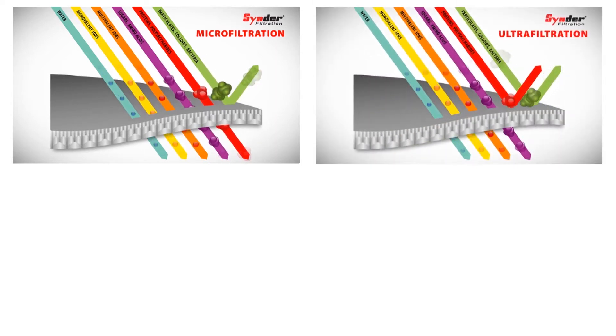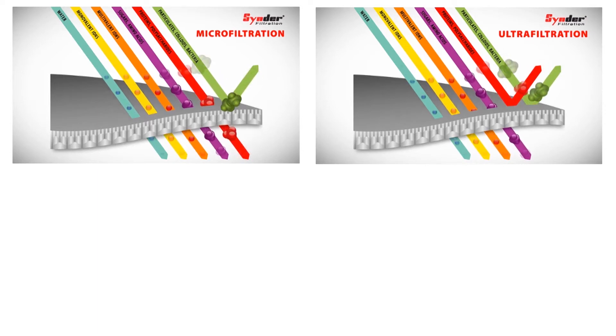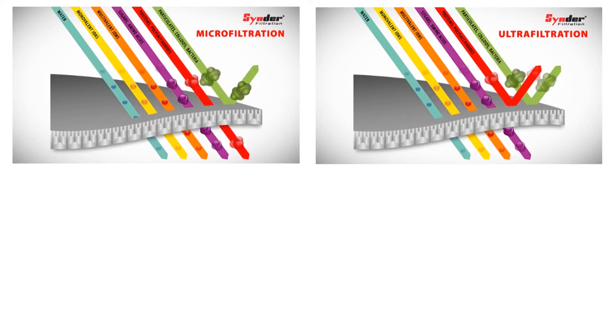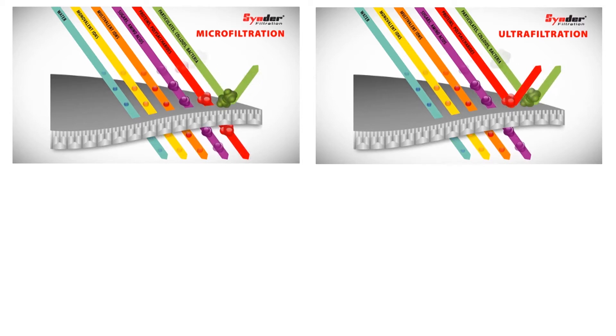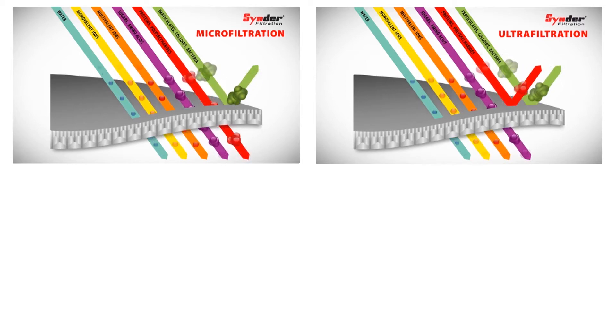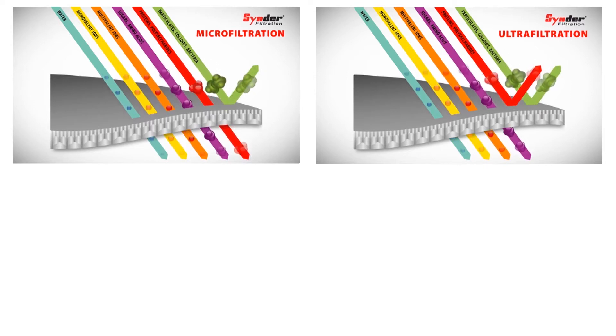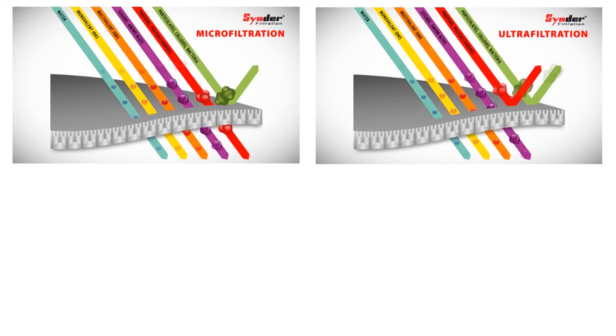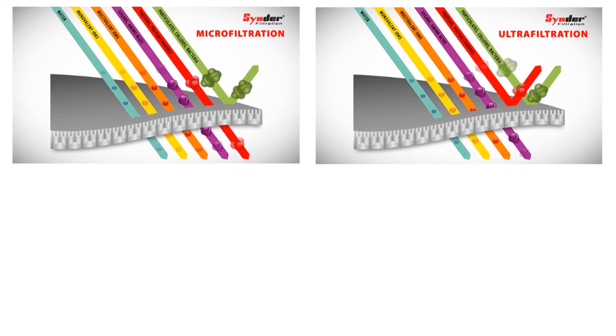Ultrafiltration has smaller pores than microfiltration membranes and can reject particles as small as 0.01 microns, which includes most viruses. So as you can see, microfiltration will reject bacteria, and ultrafiltration will reject bacteria as well as viruses.